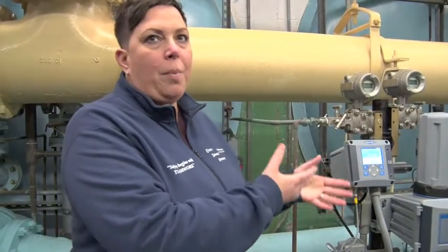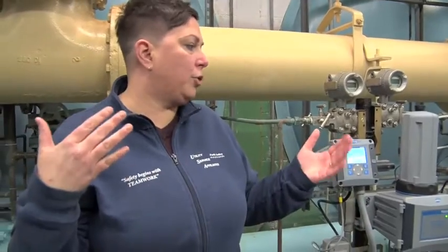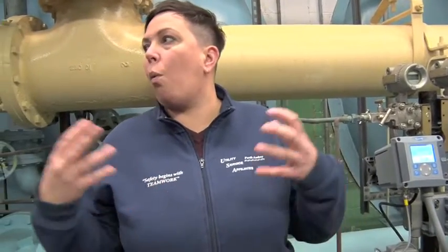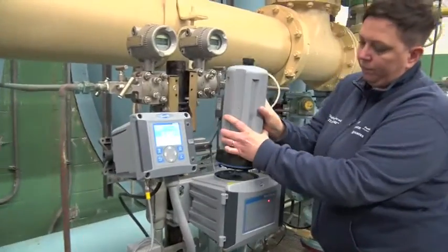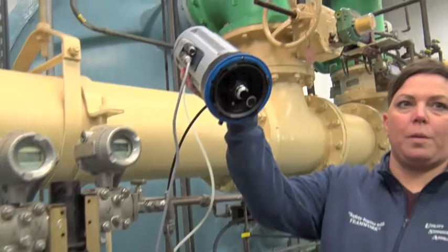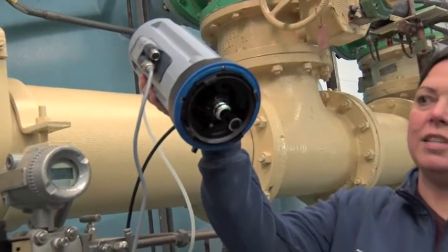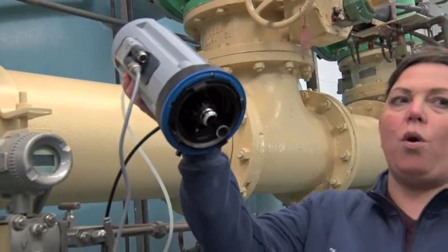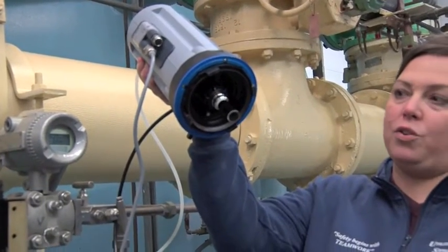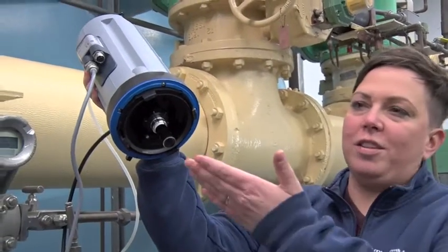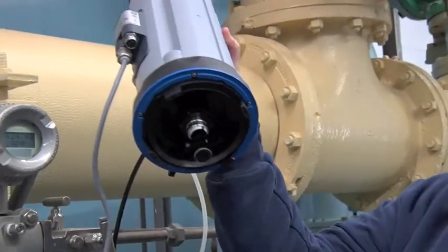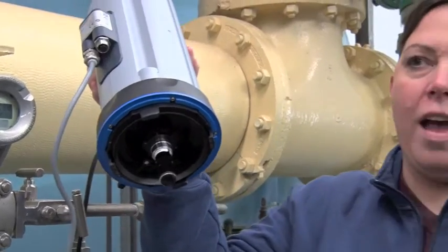What it looks like is that inside there's a vial, and there's an actual laser that runs through the vial that looks for the transparency of the water. So this is what they look like. And if you see, this is our water, our finished water, before it goes out the door. And now we take it from that water that you saw in the clarifiers to this. So this is actually analyzing this every 15 minutes.